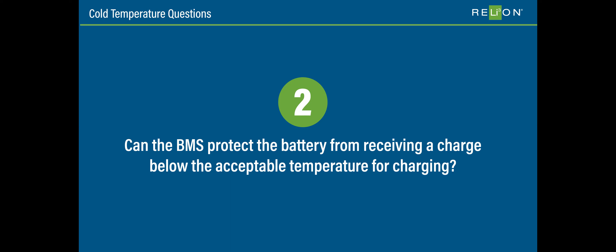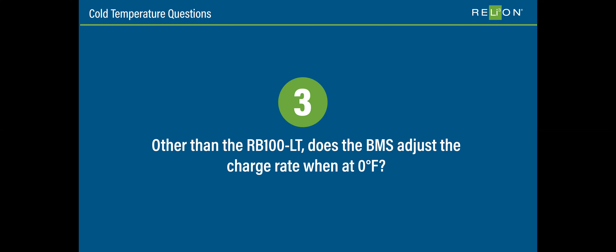Other than the RB100 LT, does the BMS adjust the charge rate when at 0 degrees F? The BMS is in all our products, but they don't adjust the charge rate when it's cold, and there's no protection there except on a few 48 volt steel case models. With the RB100 LT specifically, it also does not adjust the charge rate. Its functionality is, if we're below freezing, that battery will use the charge current to heat itself up, and then when it gets above 0 degrees F, specifically 5 degrees F, it'll allow the charge to proceed.